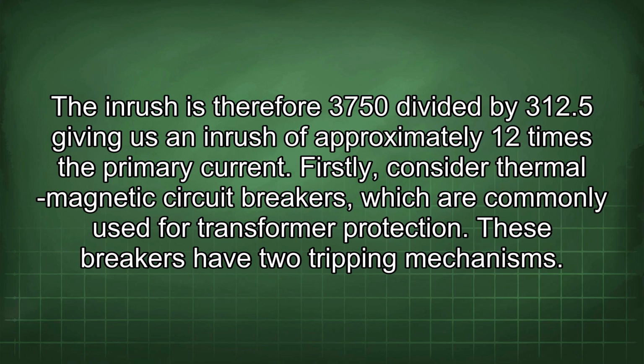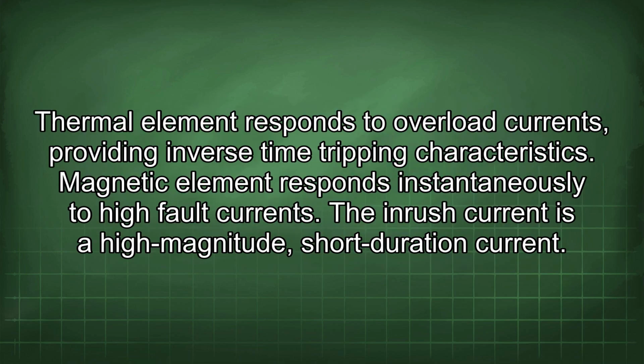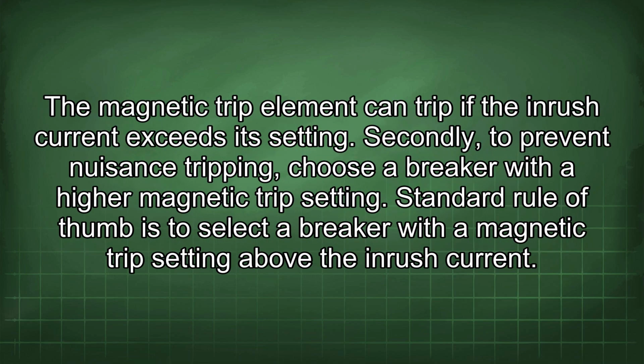Firstly, consider thermal magnetic circuit breakers, which are commonly used for transformer protection. These breakers have two tripping mechanisms. Thermal element responds to overload currents, providing inverse time tripping characteristics. Magnetic element responds instantaneously to high fault currents. The inrush current is a high magnitude, short duration current. The magnetic trip element can trip if the inrush current exceeds its setting. Secondly, to prevent nuisance tripping, choose a breaker with a higher magnetic trip setting. Standard rule of thumb is to select a breaker with a magnetic trip setting above the inrush current.